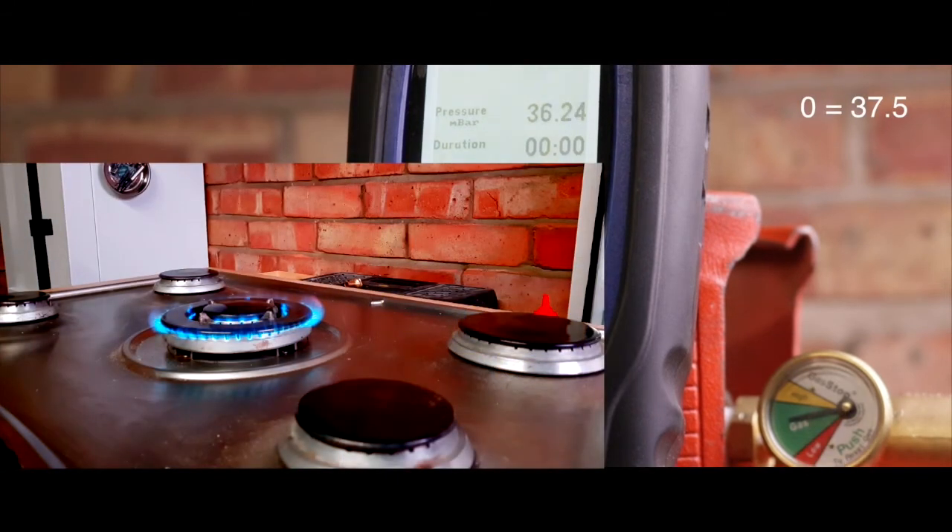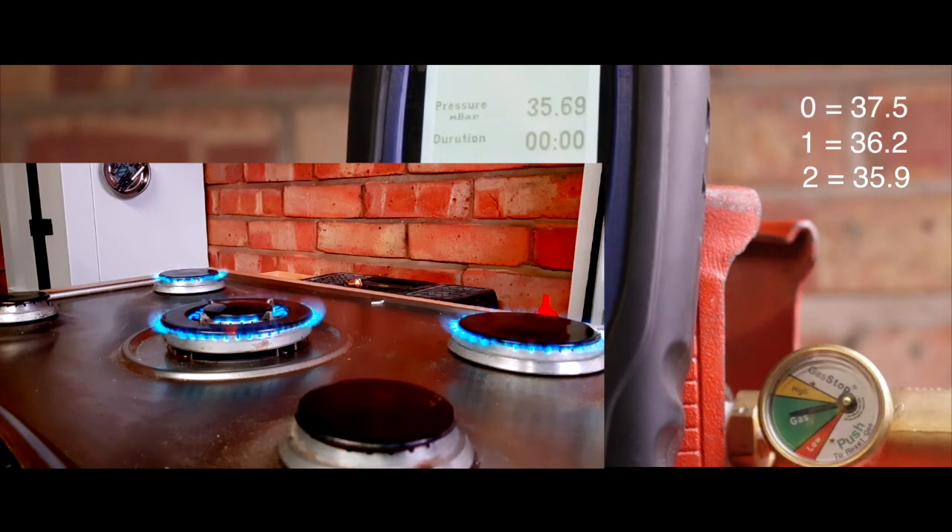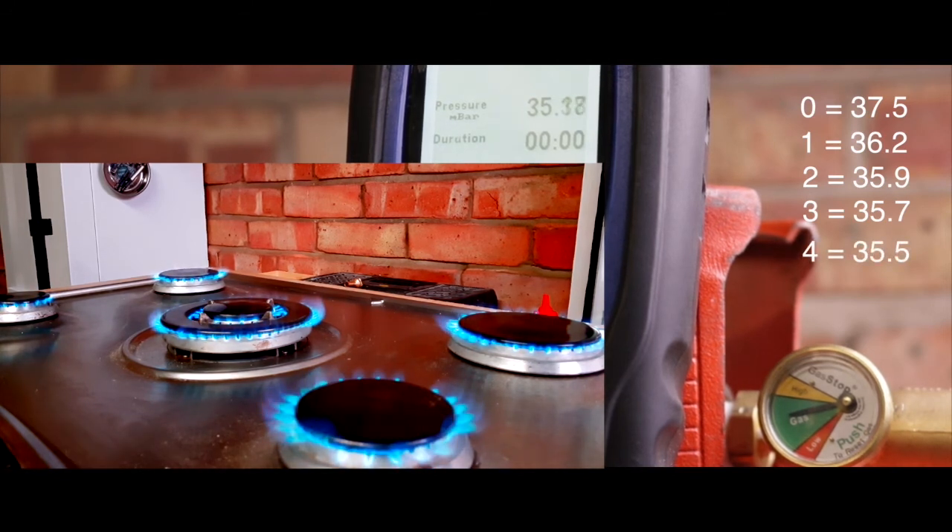36.25, which is a full 1.25 millibar less, just with the one ring. The next largest ring takes it down even further, but the valve remains the same. Which is a similar drop in pressure when using the cooker. So if the gas stop valve were calibrated to shut off minor leaks, it would shut off the appliance every time you went to use it. So we're down to 35.5 and the gas stop valve remains in the same position.